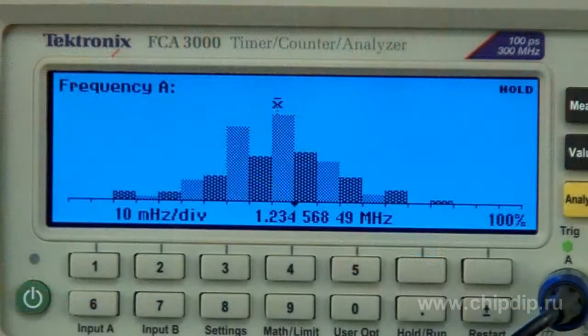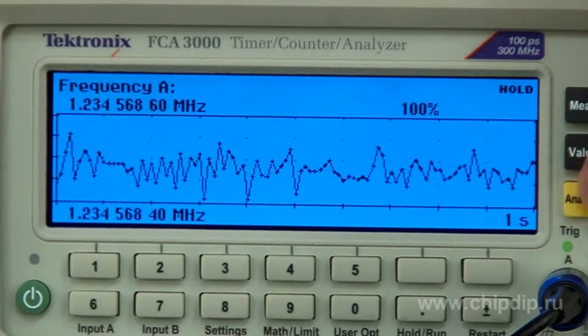The unique display of the FCA 3000 helps observe several measured parameters simultaneously without the need to reconnect the measuring terminals. To get an idea of signal quality properties such as shift, instability or stability, obtained data can be observed on the display as a graphic trend. With built-in real-time graphic histogram, measured statistical quantities can be used to see how parameters of the signal changed over time, alongside results of measurements of the main frequency.